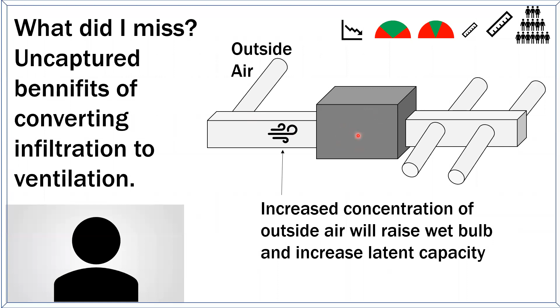And because it's more humid, you can remove more humidity from it. So things aren't quite as bad as I was showing on the page there, but that was when we were doing exhaust-only ventilation. It's really quite a good thing that we've started to bring our outside air into that return plenum, because it increases the concentration of moisture and makes my unit more efficient at removing said moisture when it's running.